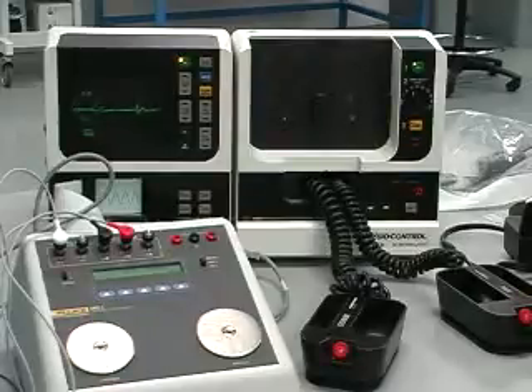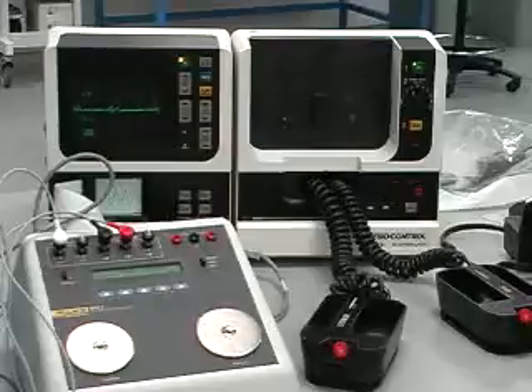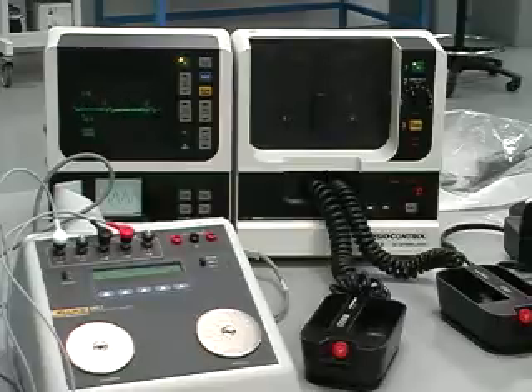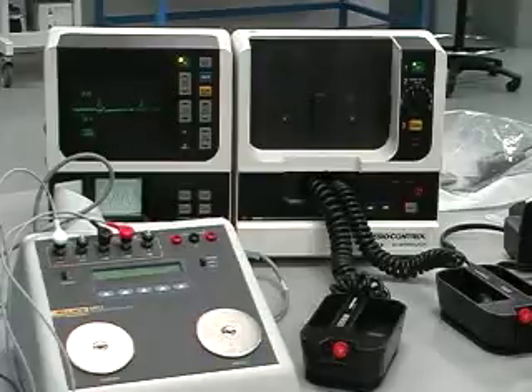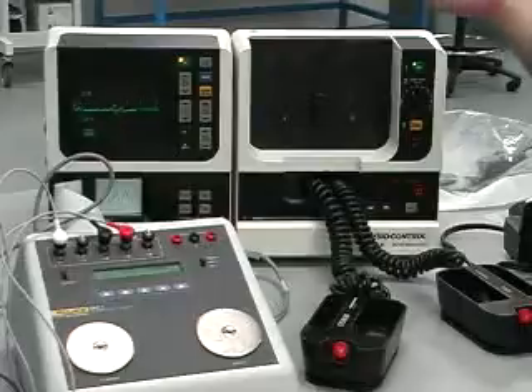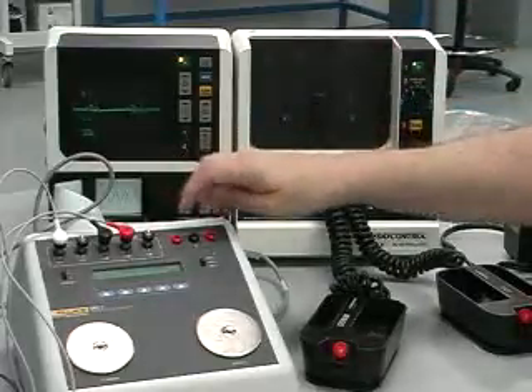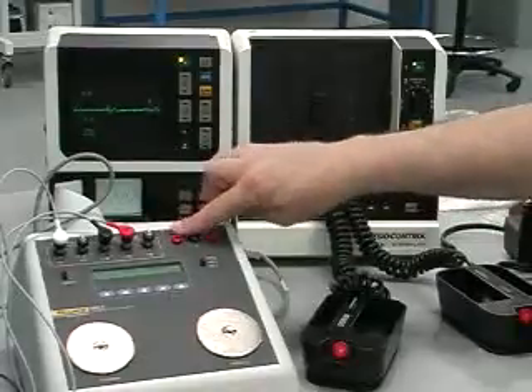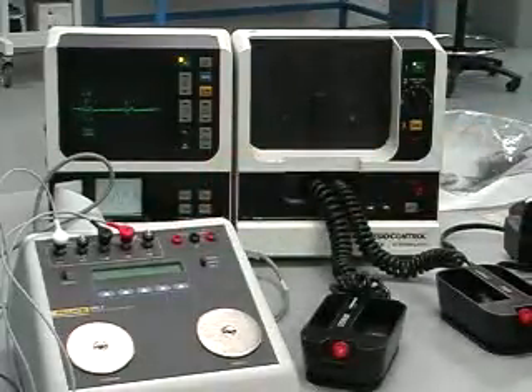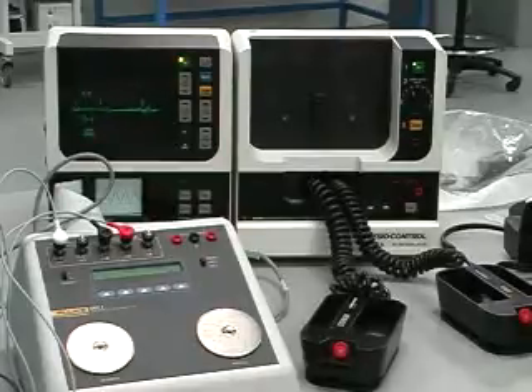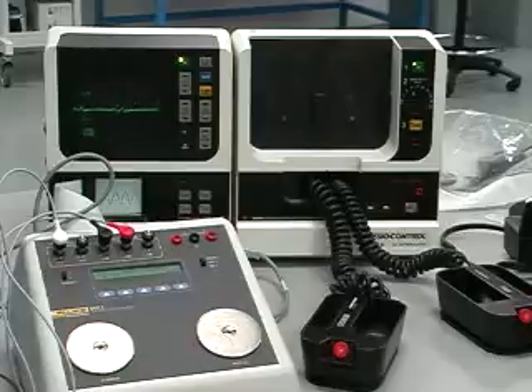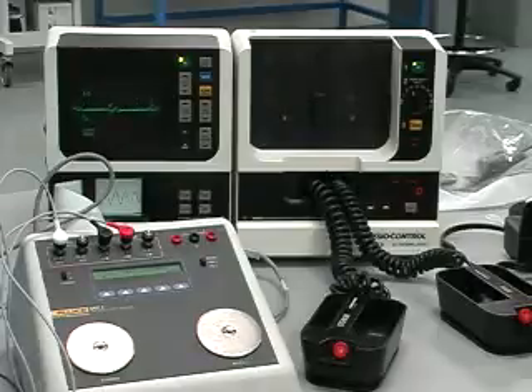Well, what they do a lot of times, there are older defibs that don't even have the synchronization feature. But if they do have synchronization capability but don't have ECG activity, a lot of times they will use a slave scope from a bedside monitor. And that's where that 1-volt ECG level would come in handy. You could take that and input that into the defibrillator. It just depends on the requirements of that specific defibrillator, what type of synchronization signal it would need to discharge it. So you have to use that defibrillator only in that room with some equipment.